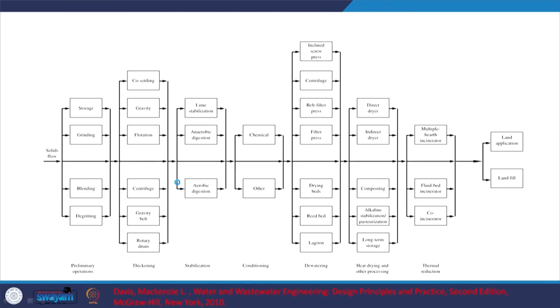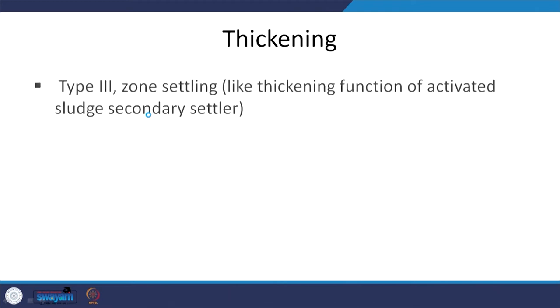Residual treatment — we are talking about thickening. We want to increase the solids concentration; gravity is the most usual and simplest method. In thickening, think of our secondary clarifier — there too you see some level of thickening. Once sludge is collected and by gravity you are going to see thickening. There are different stages: the upper stages typically show Type 1 and Type 2 settling, but most of the relevant depth you are going to see Type 3 and Type 4 settling.